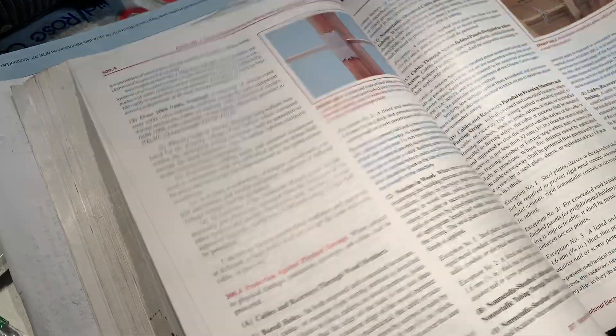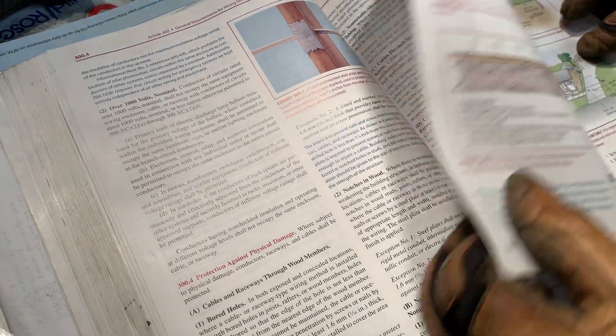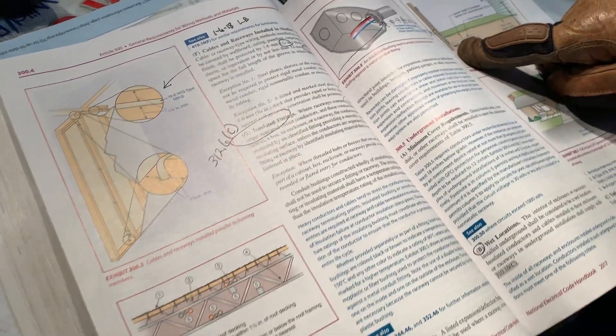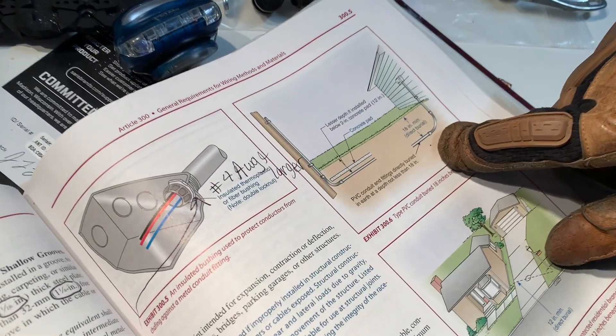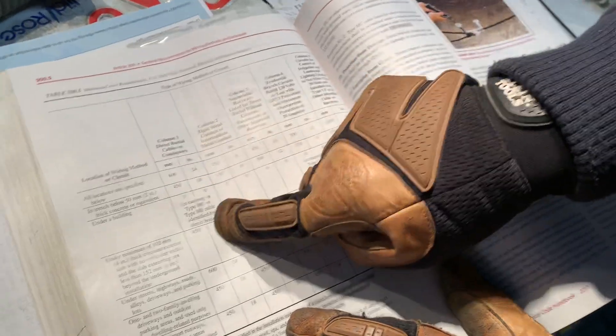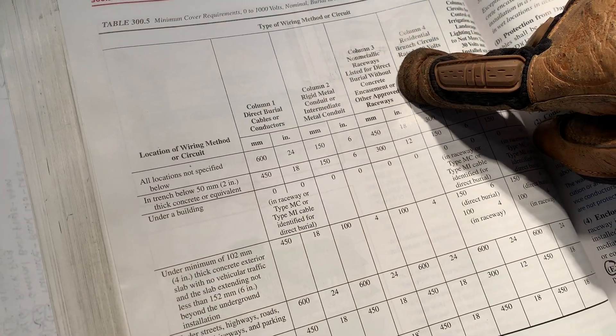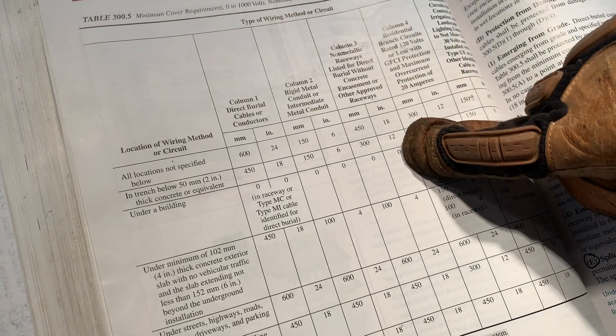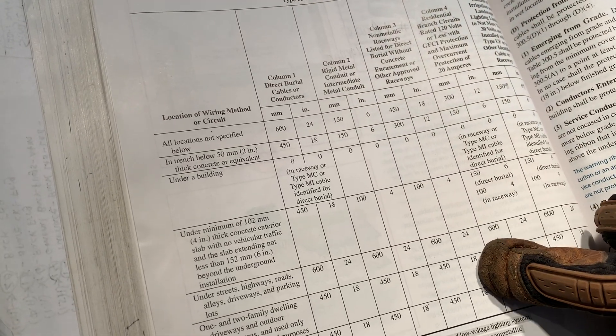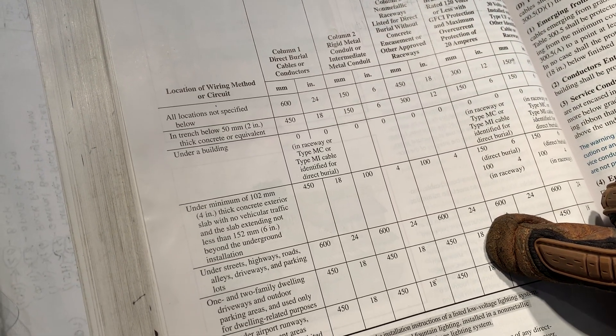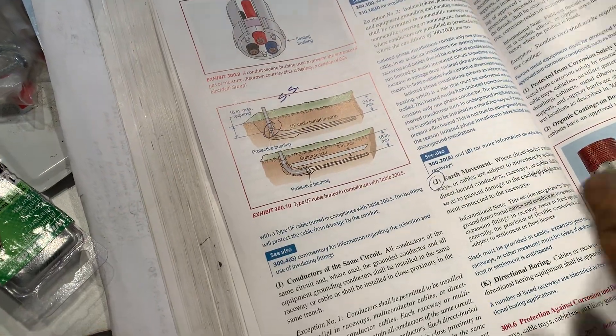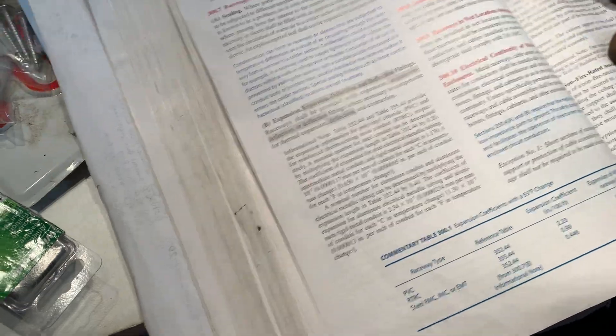Now, the other thing I saw, the mistake that they made, was outside installation. It talks about our slip sleeves coming up. 18 inches of burial for 240 volt. And that's going to talk about that in 300.5, that we are in all locations, and we're typically in a residential situation, and so we're going to be in an 18-inch column. This talks about our direct bury. They were 6 1⁄2 inches at 240 volt. That's nowhere allowed.